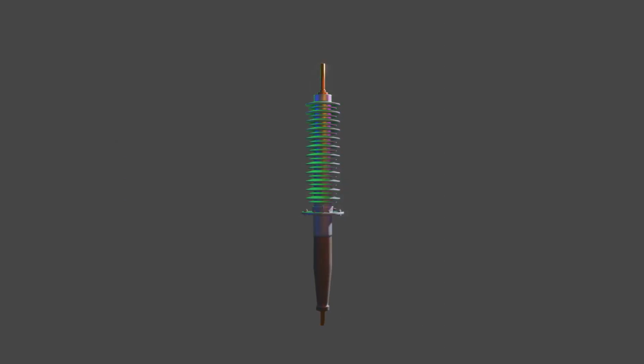In summary, a RIP bushing is built from inside out. A central conductor, then many paper and foil layers for voltage grading, all locked solid with epoxy. Because there is no oil, RIP bushings are much lighter and operate at higher temperature ratings, class E. They also need almost no maintenance, no oil to top up, and will not catch fire or explode like an oil-filled bushing. These features, together with the even voltage grading and built-in tan delta testing, make RIP bushings very durable and reliable in modern power equipment.